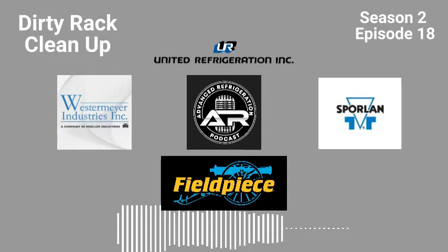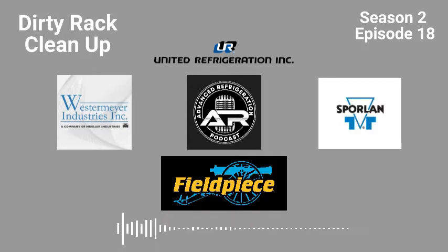So if you had technically hooked that other valve up, you would have smoked that 326, right? And then you didn't have another one, and you would have attempted to put that on there. You would have smoked the Micro Thermo port, which would have told you, hey, valve's bad. But you told me something interesting about the valve, and I want to make sure you press on this: you said the one controller ran for a couple weeks, and you had a theory why the valve was bad. My theory was, I tracked it down on Micro Thermo. It's not so much a theory. I proved it.